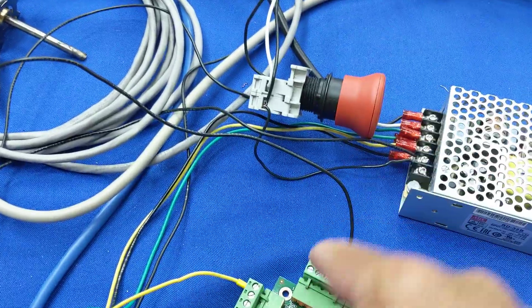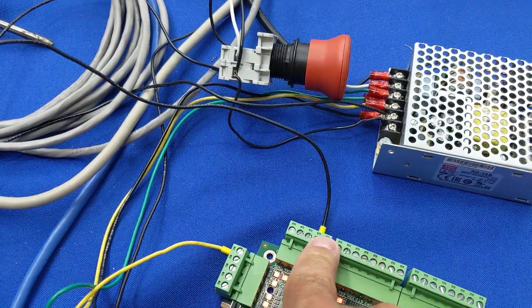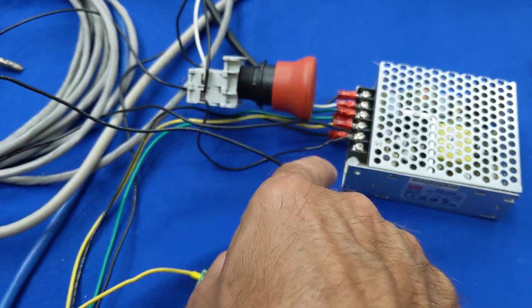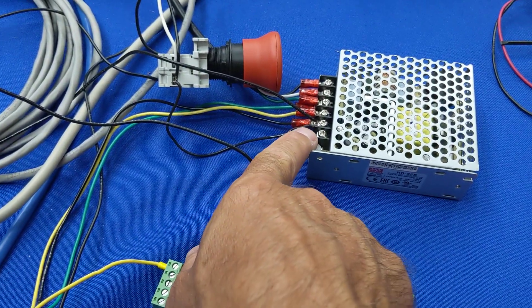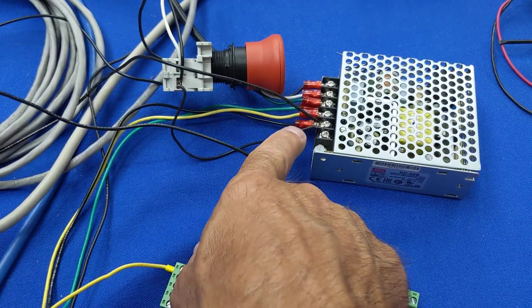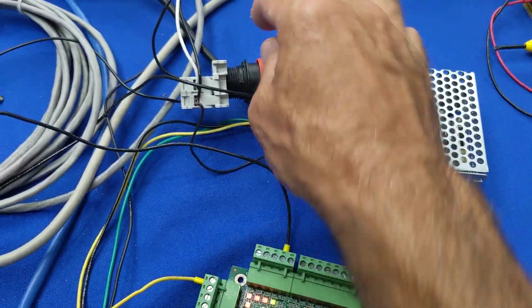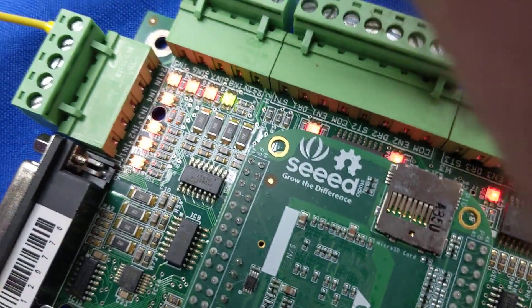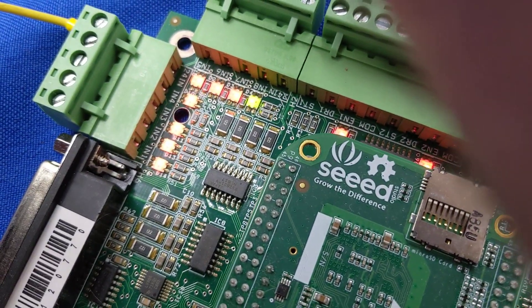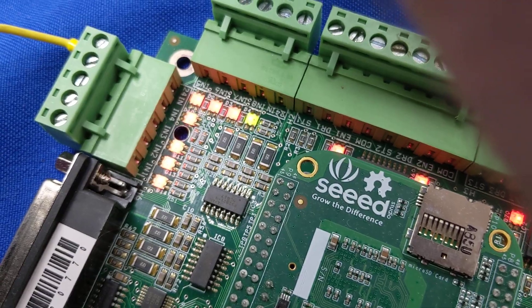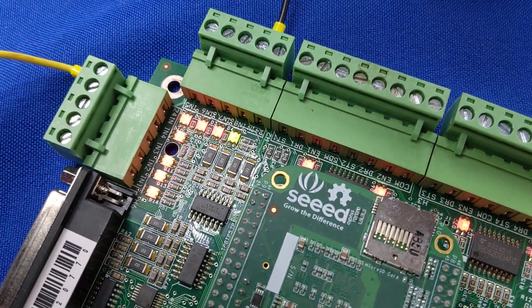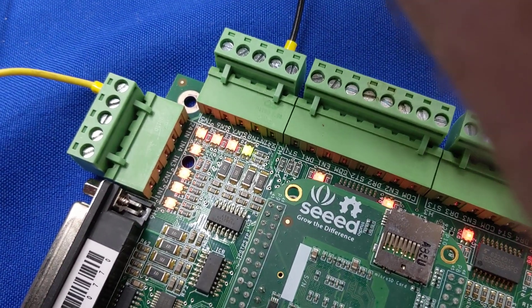So what I have here is I've got an e-stop switch that simply has this wire going to it, to input 8, to the switch, and then the other side of the switch is going to the 24 volt common or 24 volt negative if you want to think about it that way. So when I toggle that switch, watch what happens to the input 8 LED. Turns from red to green. So green means that the input is closed.